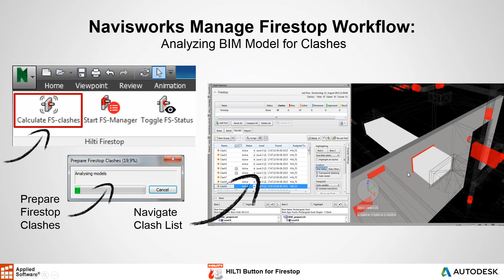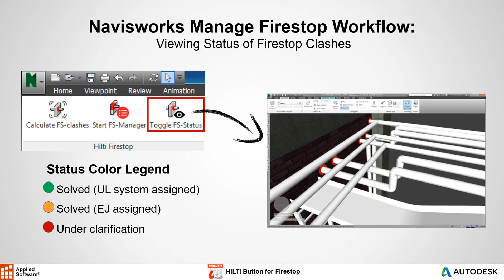When you first run the clash, the status would be under clarification — you haven't made a decision yet. When you assign a UL approved system to that penetration, it turns green, and if more investigation is needed, it's assigned an EJ status, which stands for engineering judgment, shown in yellow.